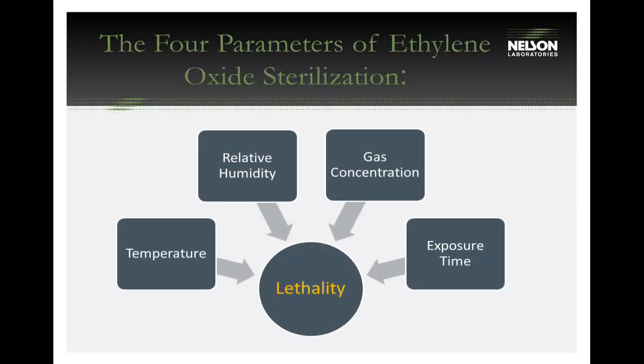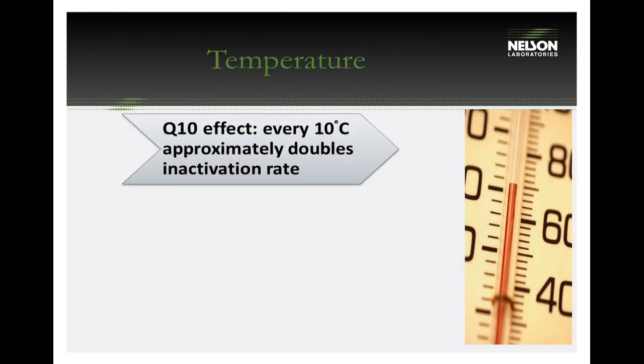There are four parameters that govern ethylene oxide lethality, and all four must work in conjunction: temperature, relative humidity, gas concentration, and exposure time. This makes EO sterilization one of the most complex methods available — compare it to radiation, which has just one parameter (dose). Because all four must be closely monitored and kept within specifications, parametric release is much harder to achieve with ethylene oxide.